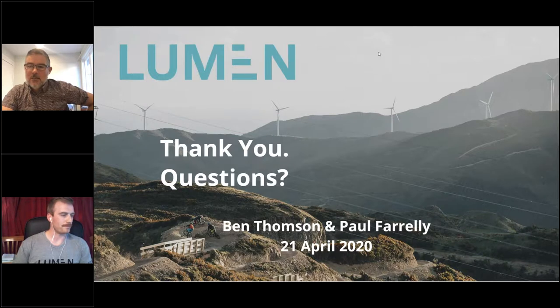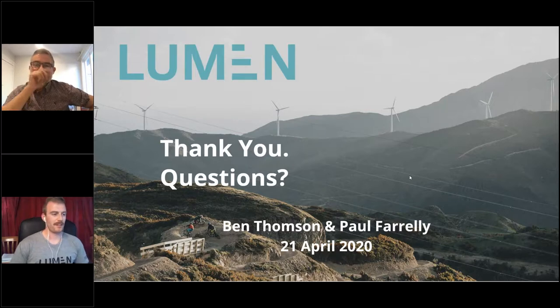Yep. There's a question there about power factor equipment. What are the options? You're probably more of an expert there than me, Ben. Yep. So power factor correction, basically it's a bank of capacitors that essentially fights against the power factor by correcting it. They're installed alongside your electrical equipment. It's a pretty common and straightforward installation. Most sites will have power factor correction if they've got a decent amount of electric motors throughout the site. So yeah, it's a really common one.